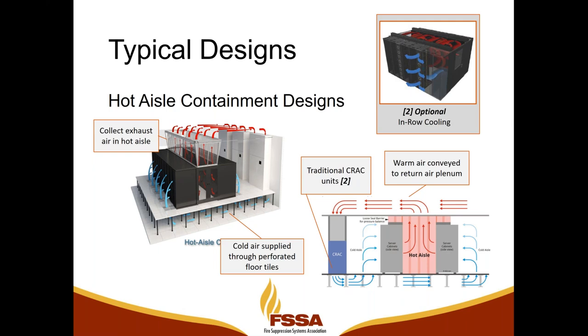So that warm air coming out of the hot aisle containment device goes up into a ceiling plenum quite frequently, or again, maybe just directly ducted back to the cooling units. What you'll often see in a data center that's deploying this, if it's an existing data center, is a project to extend the returns from the CRAC units around the perimeter of the room up to the ceiling. And that may impact some things for suppression systems with regard to how the pipes ran. So there may need to be some piping modifications to deal with those extensions up to the ceiling space.